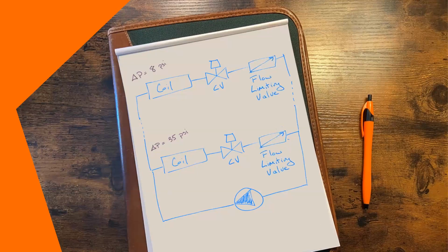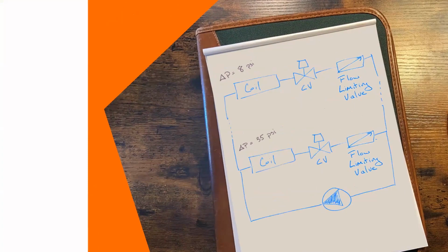So if we exchange that for an automatic flow valve or flow limiting valve, in this configuration, again, the far zone is still under control, and that close zone is balanced at full flow and protected from overflow at full flow. But it'll experience the effects of poor valve authority as flow decreases. So we've mentioned valve authority a few times now. So let's define it.